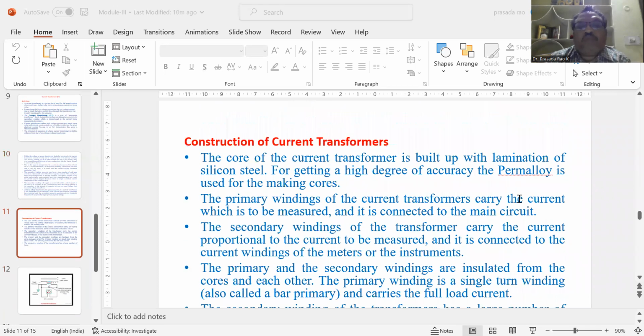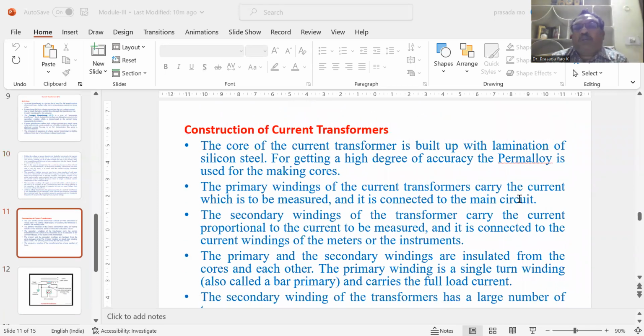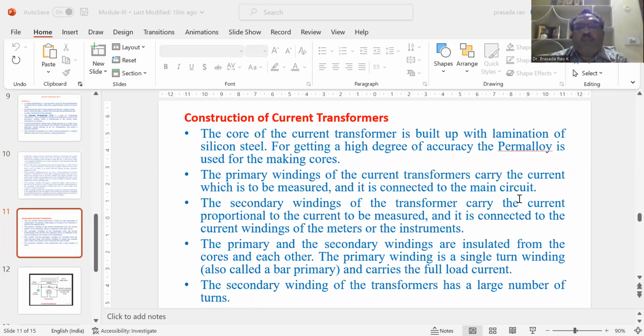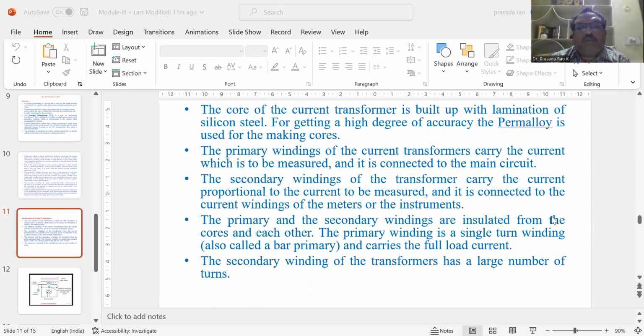The construction of a current transformer. The core of the current transformer is built up of laminations of silicon steel. For getting a higher degree of accuracy, permalloy is used for making the cores. The primary winding of the current transformer carries the current which is to be measured, and it is connected to the main circuit. The secondary winding of the transformer carries the current proportional to the current to be measured, and it is connected to the current windings of the meters or the instruments.